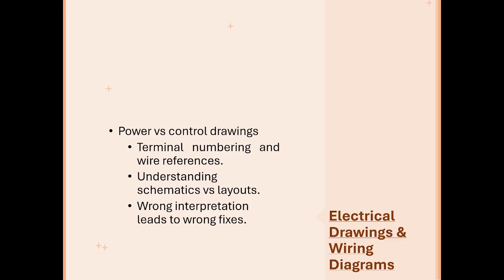So when we say power drawings, we are talking about drawings that show how equipment is energized. All right. When we say control drawings, we mean drawings that show how signals are wired between instruments, PLCs, relays, and actuators. So you will often hear the words schematic and layout. A schematic explains logic and electrical relationships, while a layout shows physical placement inside a panel or cabinet. Confusing the two is one of the fastest ways to make wrong decisions on site. So you need to understand this.